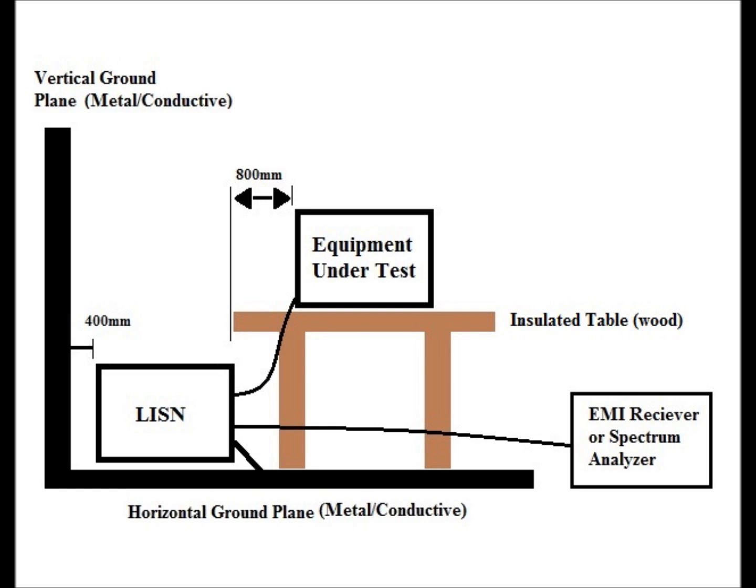We also want the EMI receiver or spectrum analyzer to be off of the horizontal ground plane, located a distance away — typically in the next room or away from the equipment under test. We basically want to minimize any capacitive coupling and any interference from other equipment with the EMI receiver and the equipment under test. The idea of using the LISN is that we want to read only the conducted emissions coming out from the equipment under test.